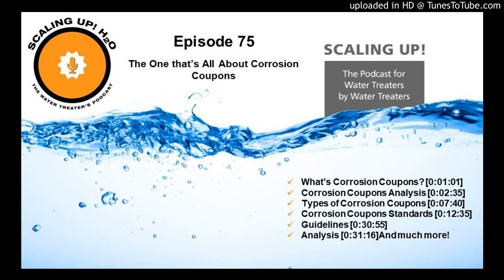Now, do you use corrosion coupons in all systems? Well, if you can, why not? Some people will ask, I've got a chiller, or this expensive piece of equipment, and I'm using corrosion coupons in that, but in a closed loop system I don't use corrosion coupons. Well folks, if you're treating the water within a system that has metal in it, I'm pretty sure that's every system. If you're not using corrosion coupons, your default is whatever that expensive piece of equipment is, that now has become your corrosion coupon. So when it develops a problem, that's your alert that there's a problem in the system.